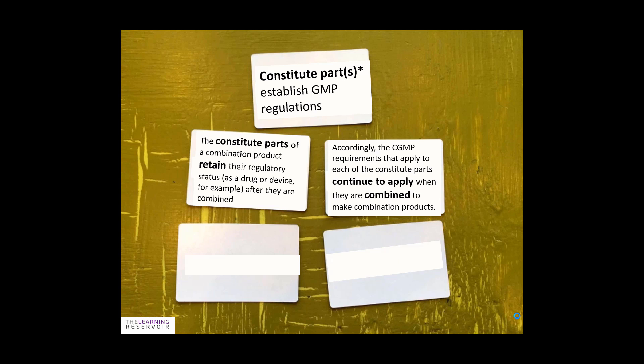So even though they go into one product to form a combination product, they are always viewed as being a combination of a drug or device. That's never forgotten — that's really important to remember. They retain their regulatory status as a drug or device even though they are now a combination product. Accordingly, the CGMP requirements that apply to each of the constituent parts continue to apply when they're combined to make the combination product.